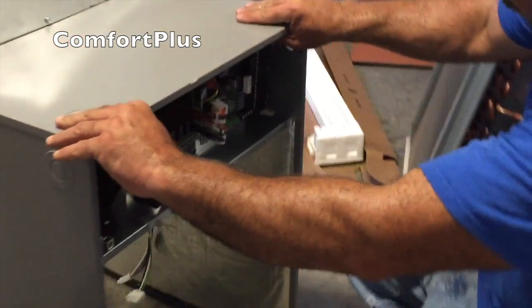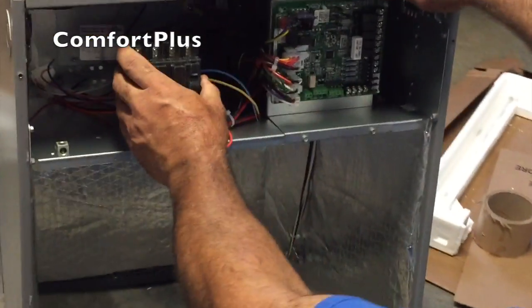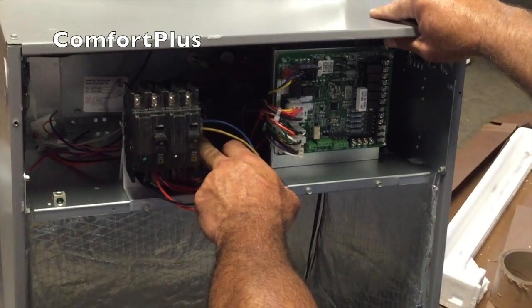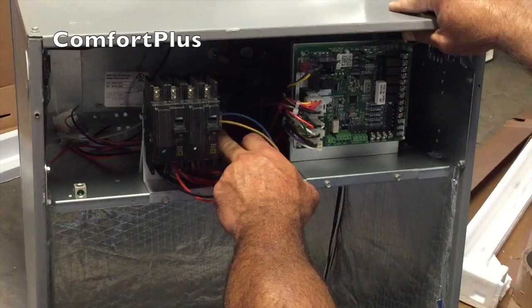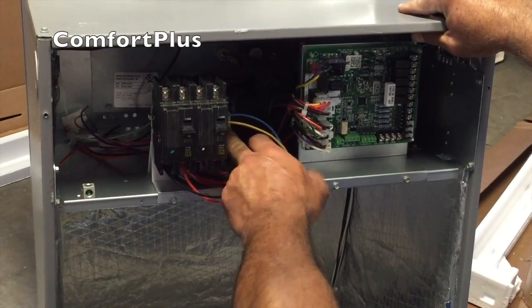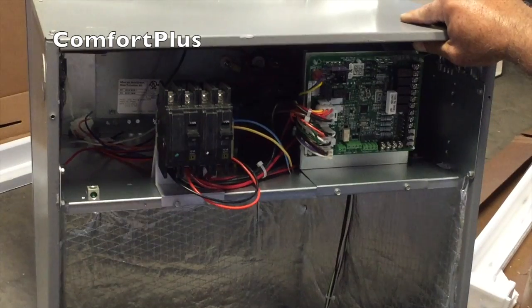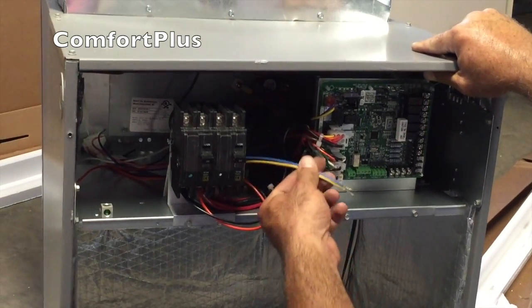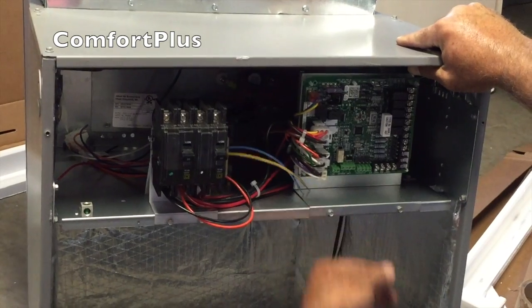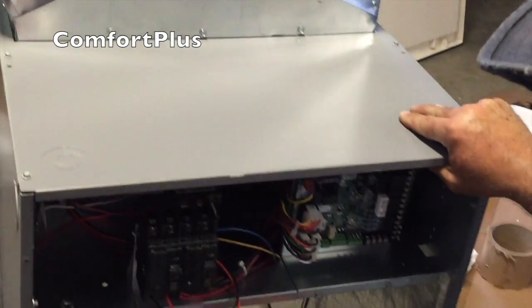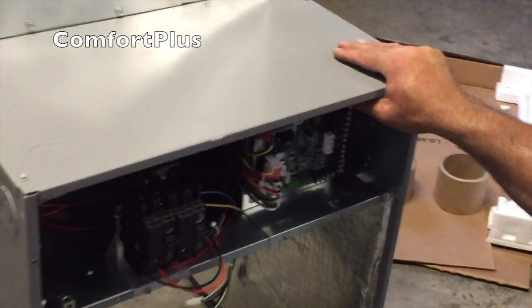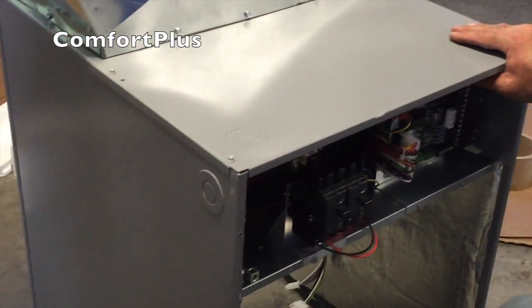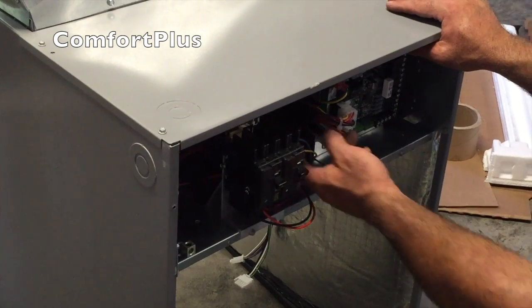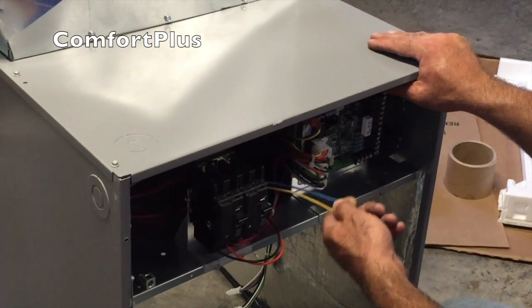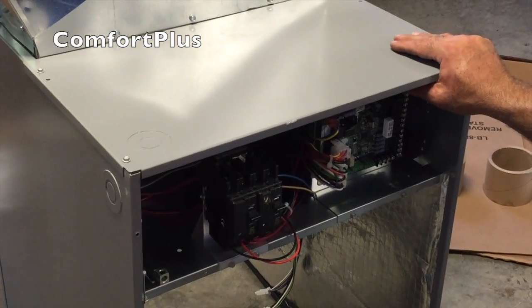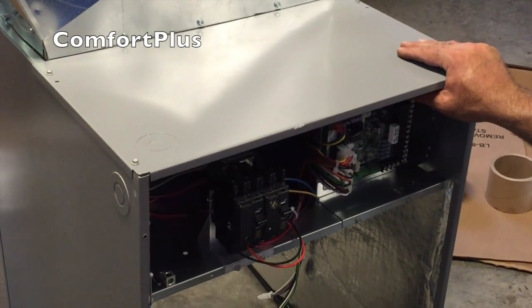Down in here, you have the control board and the breakers. I went ahead and mounted a transformer in here for the zone dampers. I just pulled power right off this main 30 amp breaker for it. We'll have these two 24 volt wires. I've got to pick up a pressure switch out of this air handler anyway to go to the zone board. So what I'll do is run a 4 conductor wire, pick up the 2 leads off the pressure switch, pick up the 2 24 volt leads for the zone damper control board and dampers, and run them up to where I mount my zone panel.